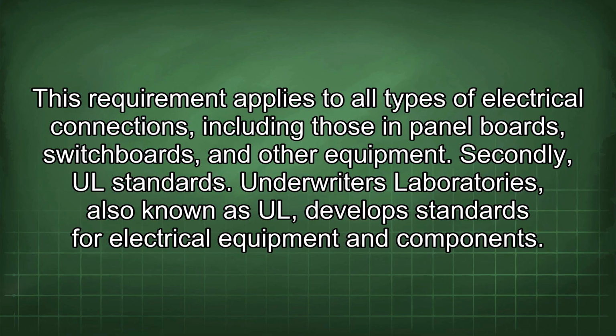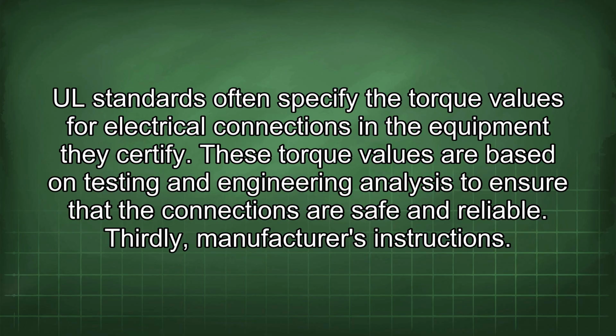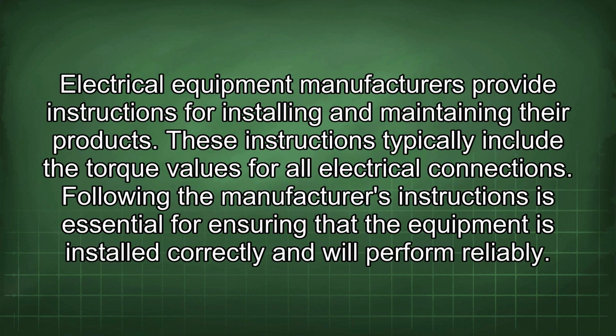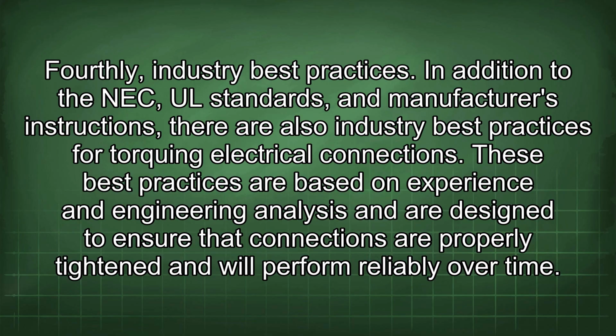Secondly, UL standards. Underwriters Laboratories, also known as UL, develops standards for electrical equipment and components. UL standards often specify the torque values for electrical connections in the equipment they certify. These torque values are based on testing and engineering analysis to ensure that the connections are safe and reliable. Thirdly, manufacturer's instructions. Electrical equipment manufacturers provide instructions for installing and maintaining their products. These instructions typically include the torque values for all electrical connections. Following the manufacturer's instructions is essential for ensuring that the equipment is installed correctly and will perform reliably. Fourthly, industry best practices. In addition to the NEC, UL standards, and manufacturer's instructions, there are also industry best practices for torquing electrical connections.